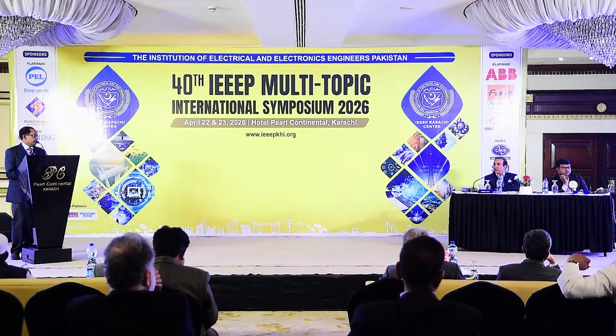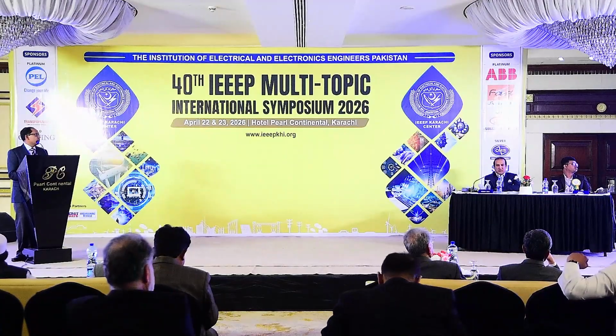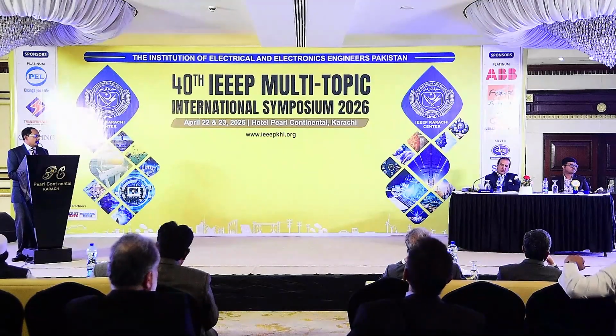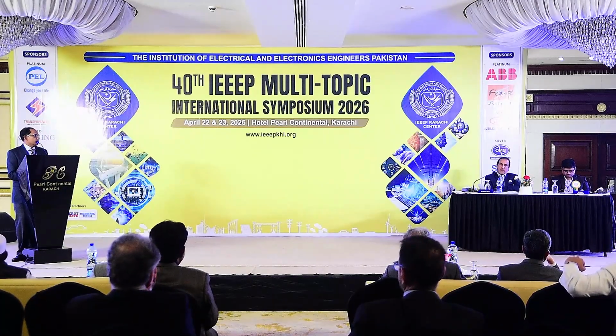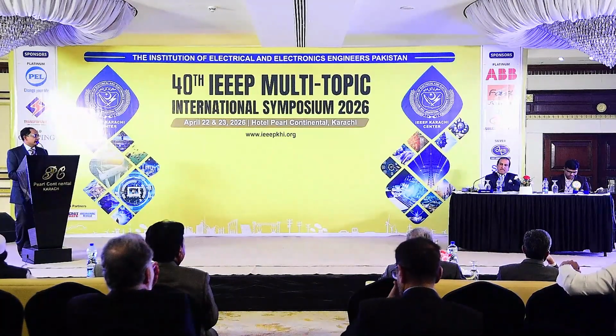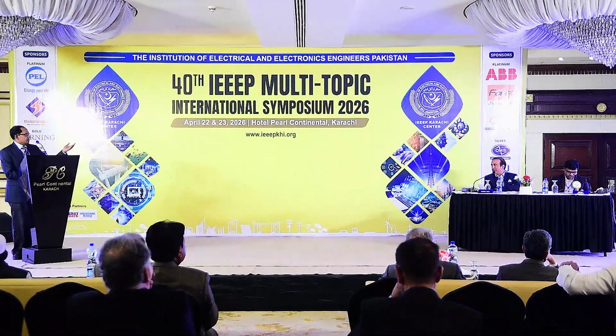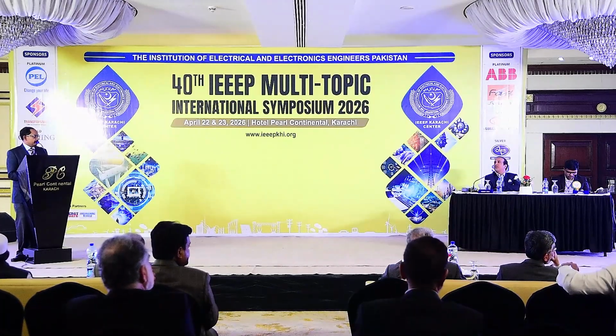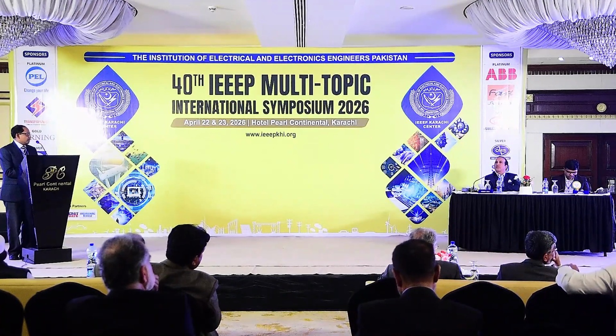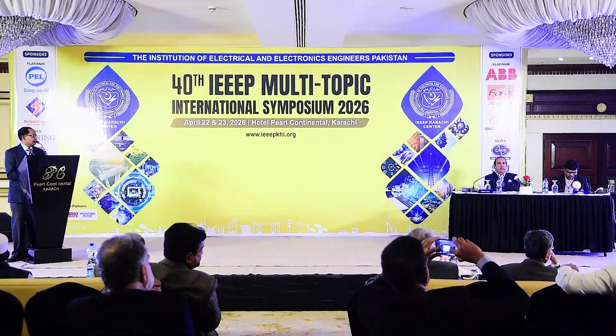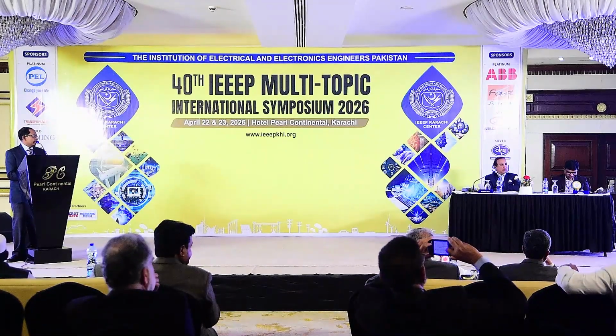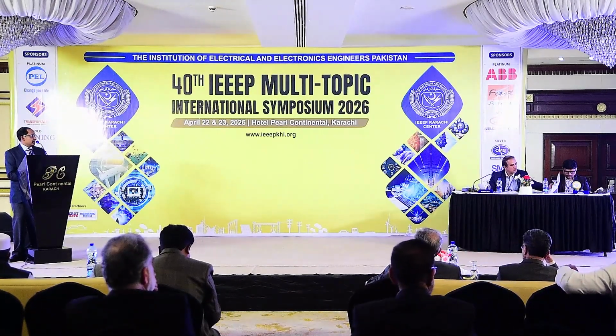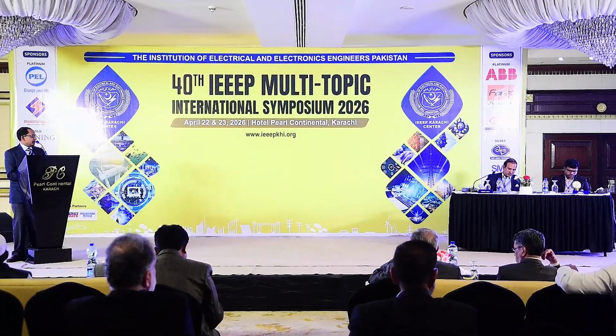Next is the PID control. In a grid following droop control system, the PID controls on the difference between a reference set point from the droop characteristics and the measured grid parameters. Below we show a block diagram which elaborates the droop control mode, the renewable generating units, and the power measurements.